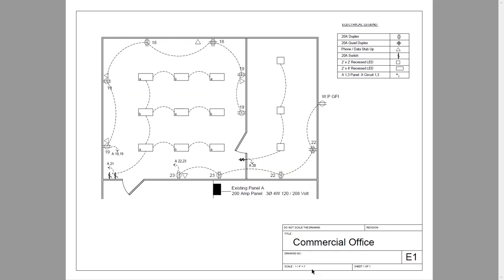The very bottom in tiny letters shows the scale at a quarter inch equals one foot. Blueprints are two-dimensional drawings — this is a top view. There's no mention of how high the ceiling is in this space. We're going to imagine it's a nine-foot ceiling, but it doesn't say that on this drawing. Sometimes on electrical drawings it doesn't show ceiling height — you have to go to architectural drawings for that.